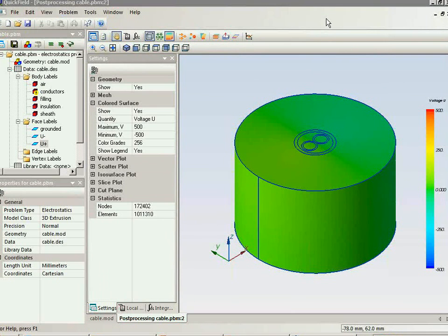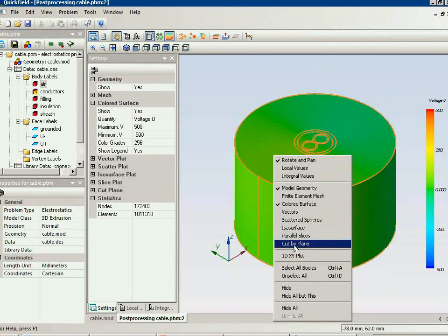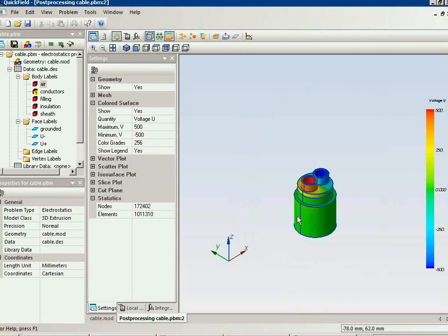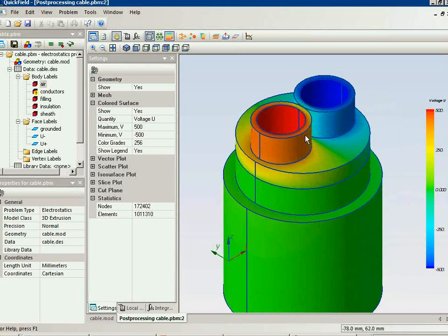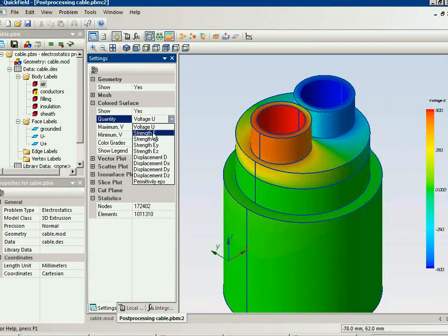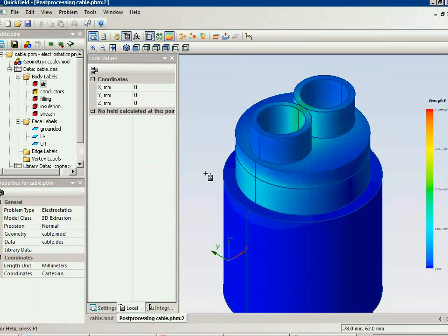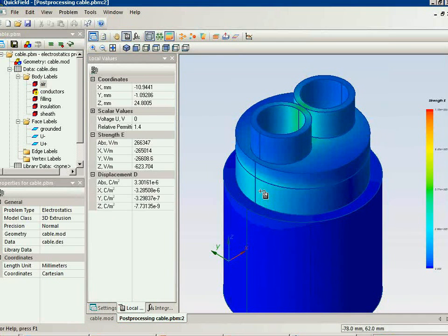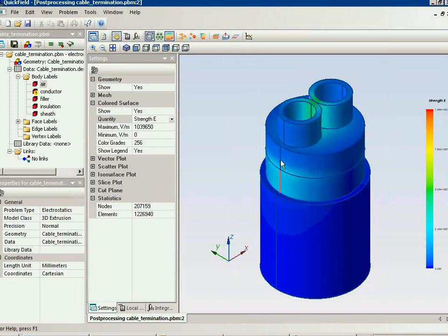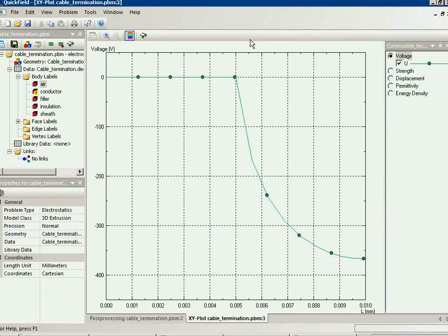Now the field is calculated and we can see the electric potential distribution. Let's hide the air block and take a look at our cable. You can see the electric potential distribution on the cable surface at the cable termination. I can change the value to electric field strength. I can get the local values and build an X-Y plot. Here you can see the electric potential distribution, and at the point where the screen is removed we have the high value of the electric field strength.